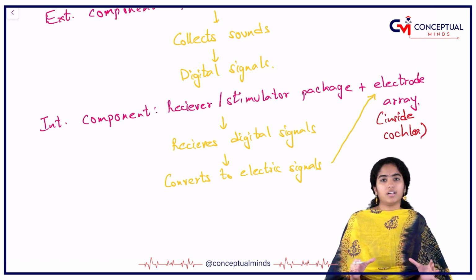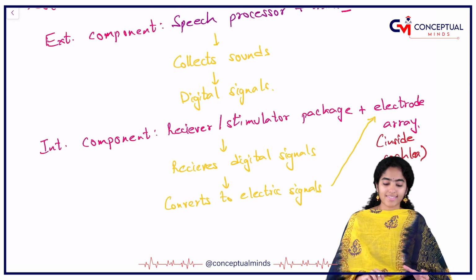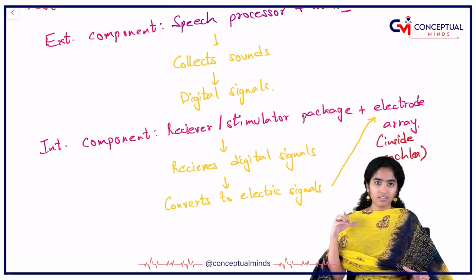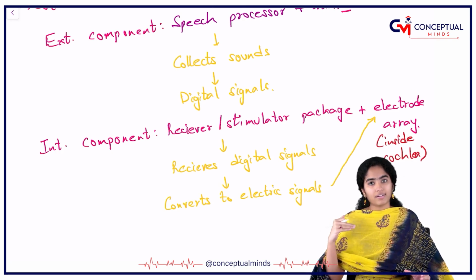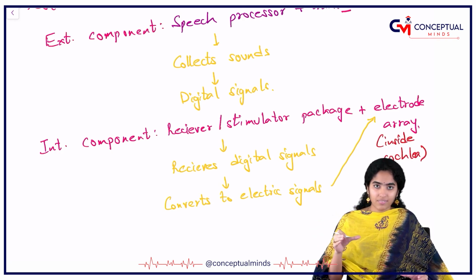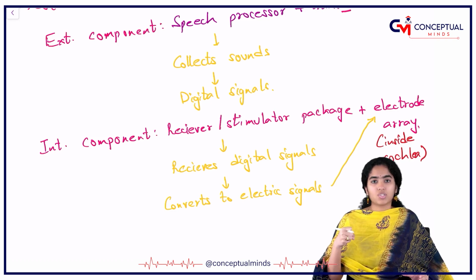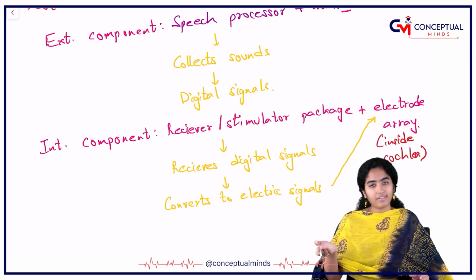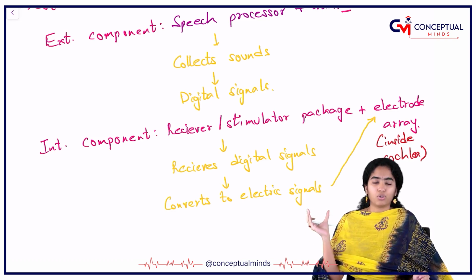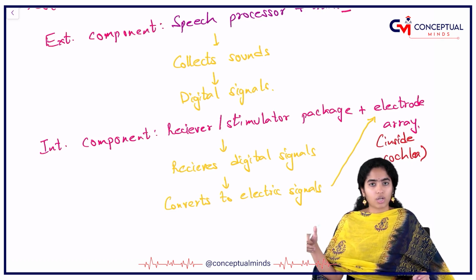Is this clear to all of you? The external component has a speech processor that picks up sounds, converts it into digital signals. Via the transmitter, it sends it to the receiver. The receiver will collect these digital signals, convert them into electrical signals and stimulate the electrode array that is present in the cochlea.